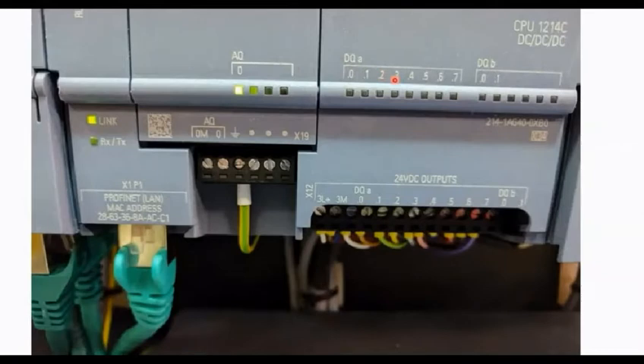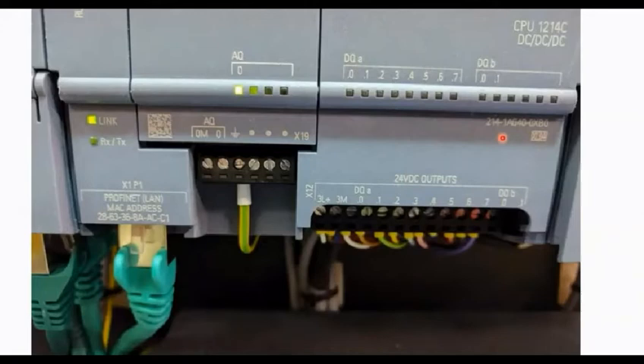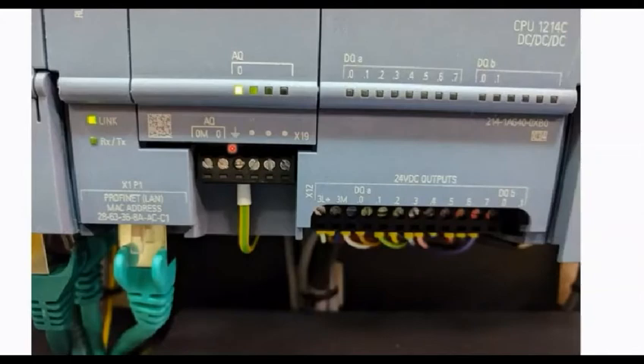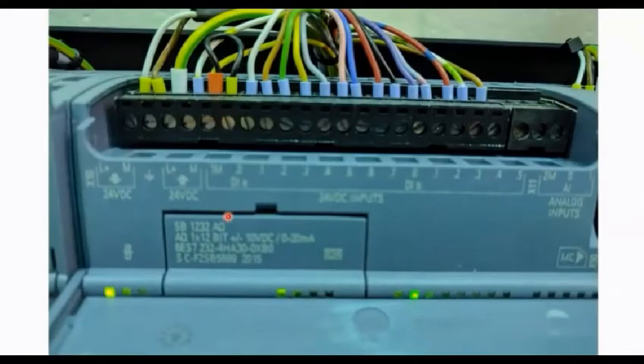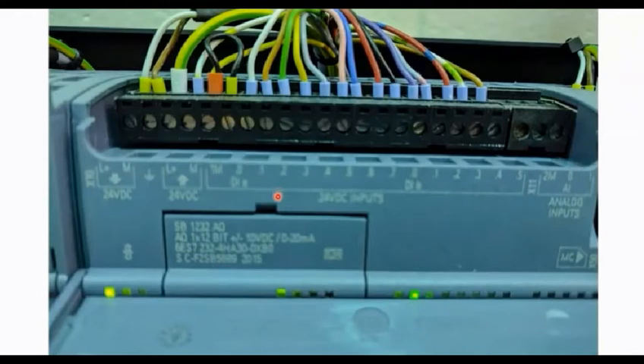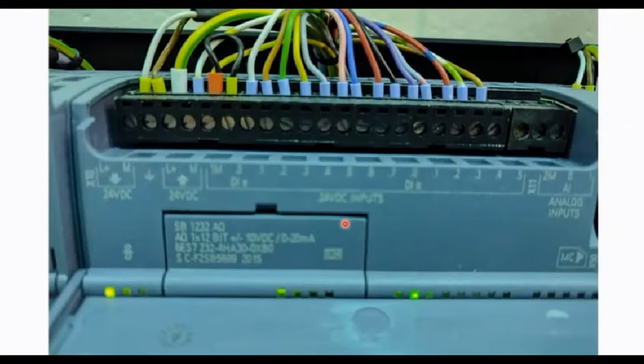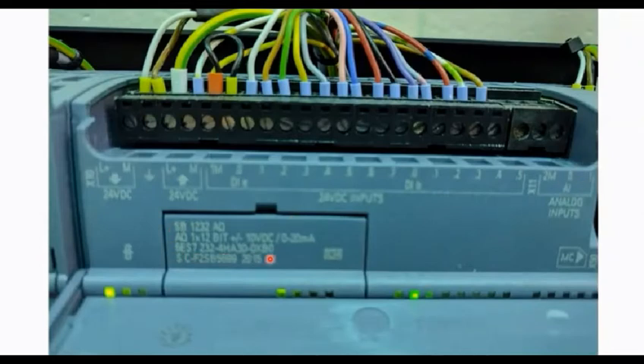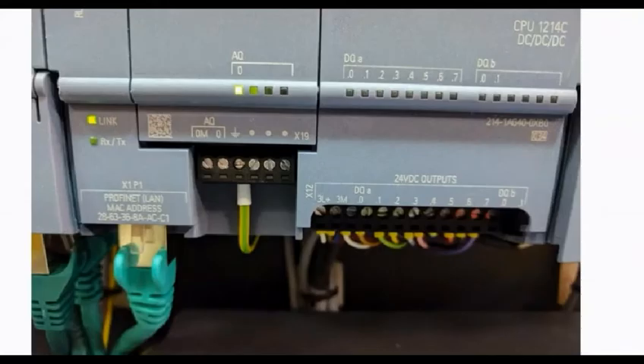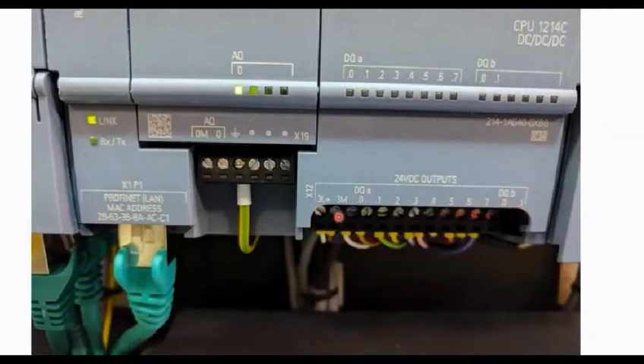Here is the DQ. DQ actually showing that in our Siemens output is showing with Q. So that's why it's showing here Q and upside you see the I, D, I mean input that in Siemens PLC ladder diagram, when you are doing the programming, you need I for input and Q for output. And this DQ is for the output. If you are doing, that is syncing, you see this card, I already told you, if you remove this cover, you can add here one analog output. So you can easily, easily, no need any scaling or no need anything you directly connect here, your analog. That is analog is 0 to 20 milliamp, plus minus 10 volt DC, you can add here.